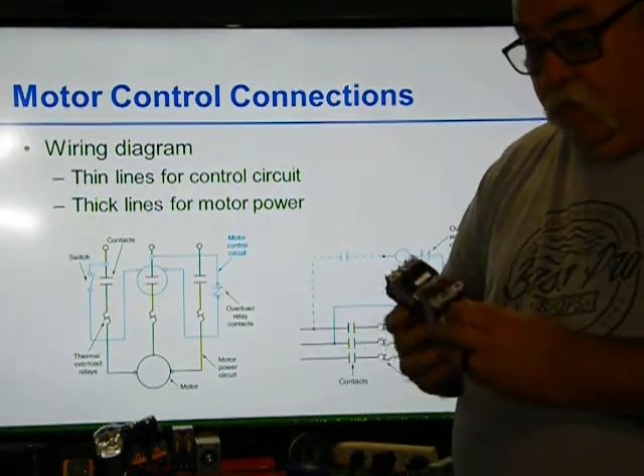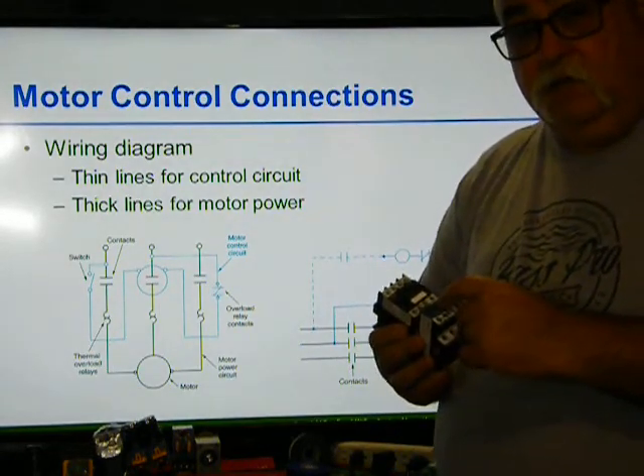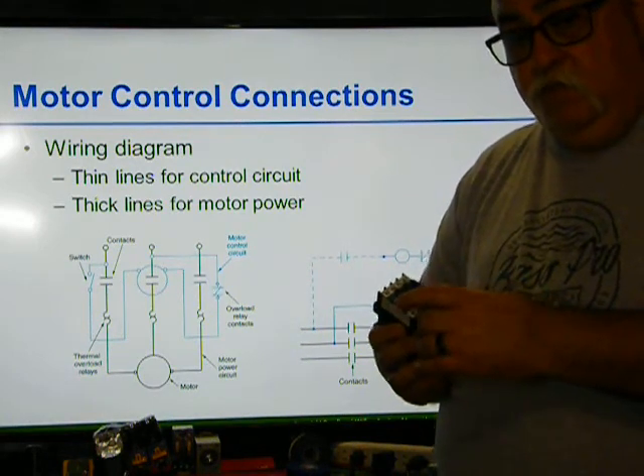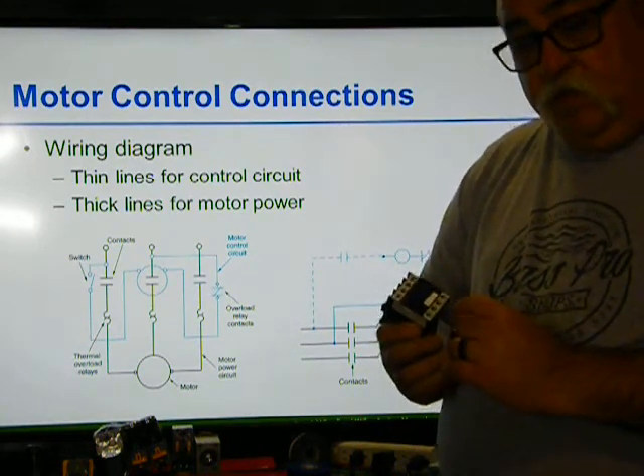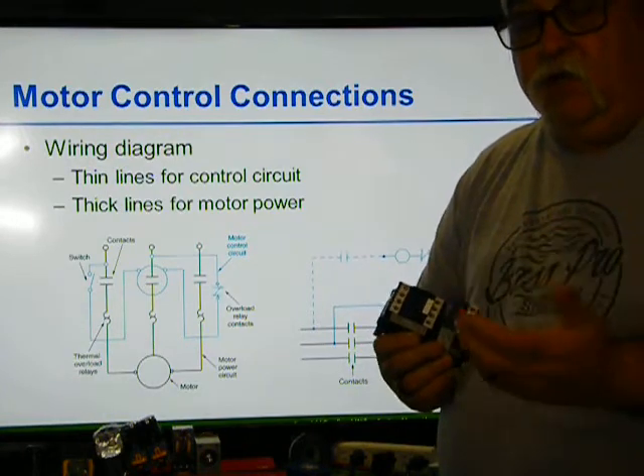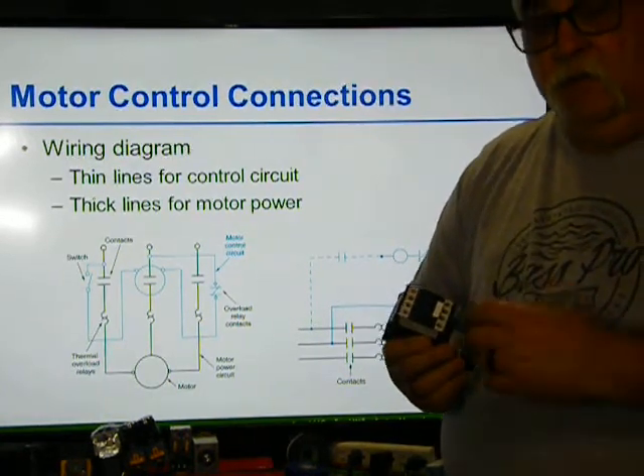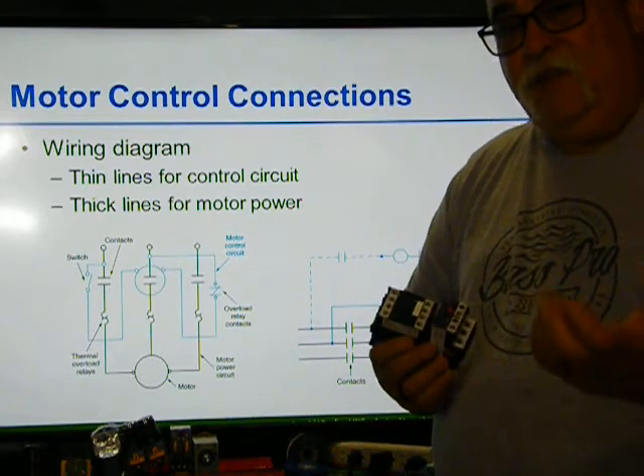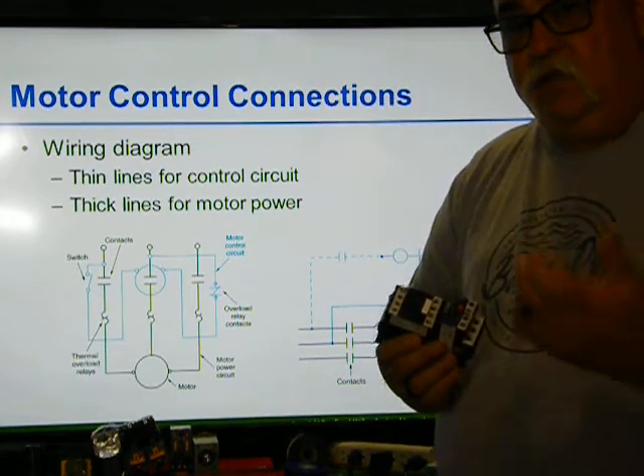What does this do? If this overheats, this is your overload protection. This is what's protecting the motor. So this is sensing that current. All it's doing is sensing heat. That's what we call them, heaters. The overloads, that's what we call them, heaters. They're sensing that heat, the current. They're not reading current, they're sensing that heat.